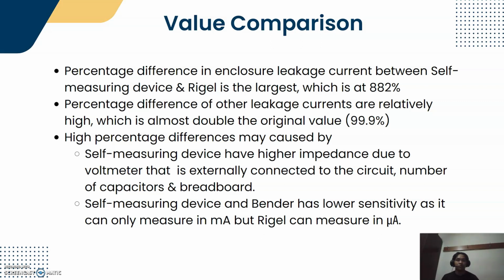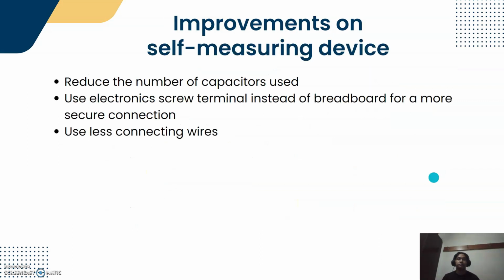The self-measuring device and the Bender also have lower sensitivity as they can only measure in milliampere, but the Rigel can measure up to microampere. So our suggestion for improving our self-measuring device is to reduce the number of capacitors used by using a single capacitor that has a value of 0.015 microfarad. Also, we can use electronic screw terminals instead of a breadboard for a more secure connection and less impedance, and we can also use fewer connecting wires.